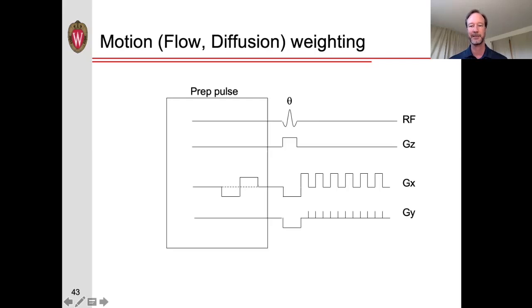So we can then repeat this procedure, applying gradients in the bipolar gradients in the other directions in order to encode the directions that the magnetization is either flowing or is diffusing, is moving around. And this is the basis for diffusion-weighted imaging, and Dr. Andy Alexander will get into a lot more detail on that in his lecture.